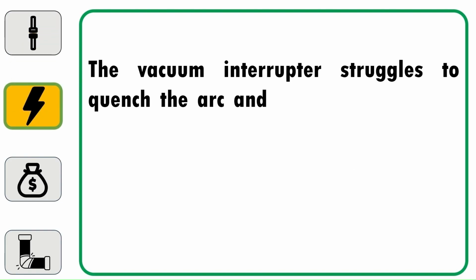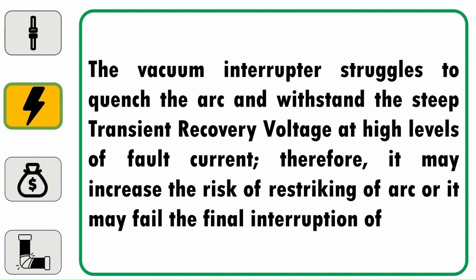VCB interrupts current by extinguishing the arc in the vacuum, which works well for moderate fault current, that is up to 40 to 63 kiloampere. But in very high voltage systems, fault current can be much higher, which is around 80 to 100 kiloampere. While interrupting this level of high fault current, it can create a high transient voltage across the contact. The vacuum interrupter struggles to quench the arc and withstand the steep transient recovery voltage at these levels. Therefore, it may increase the risk of restriking of arc, or it may fail the final interruption of arc.